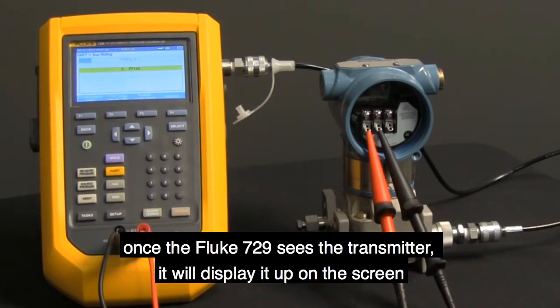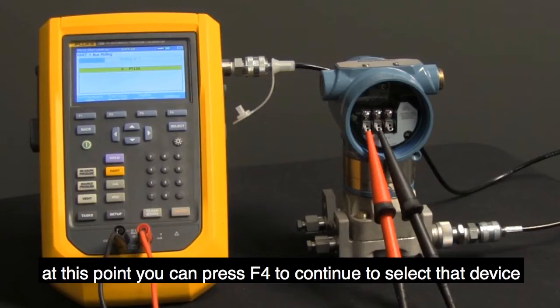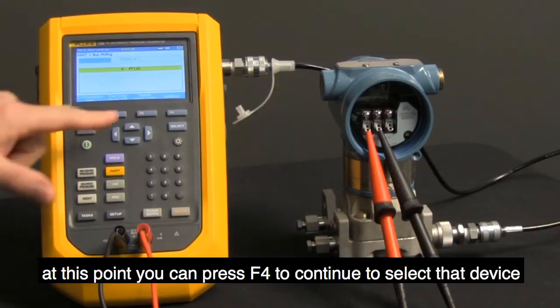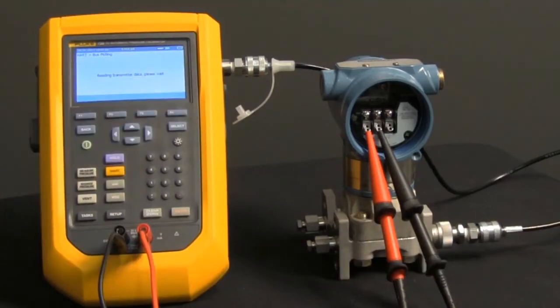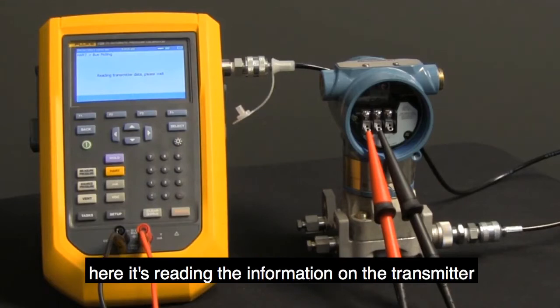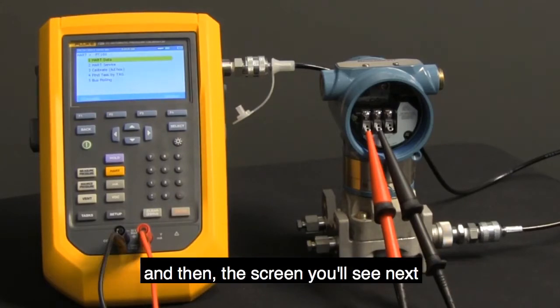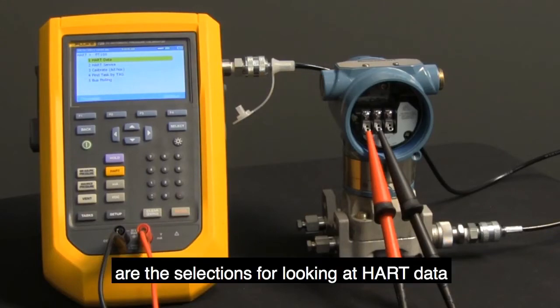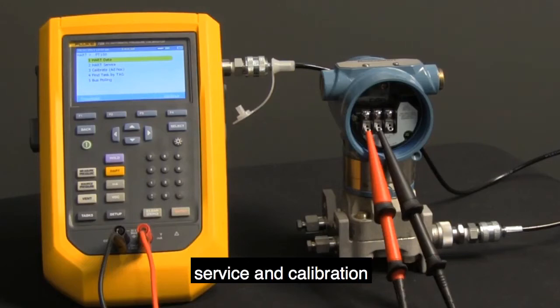Once the Fluke 729 sees the transmitter, it will display it up on the screen. At this point, you can just press F4 to continue to select that device. Here it's reading the information on the transmitter. The next screen shows selections for looking at HART data, service, and calibration.